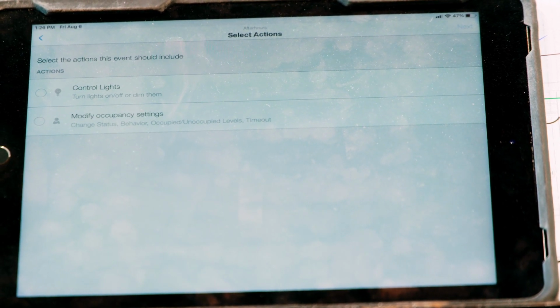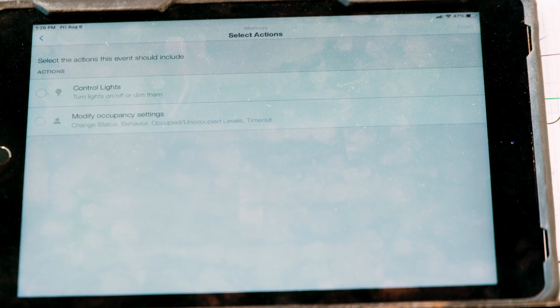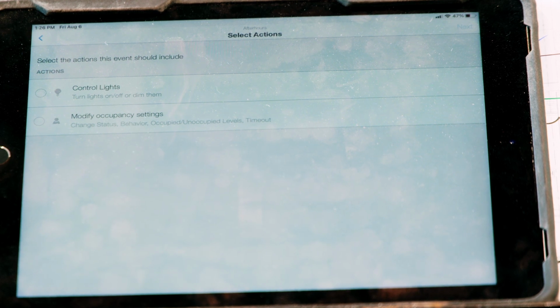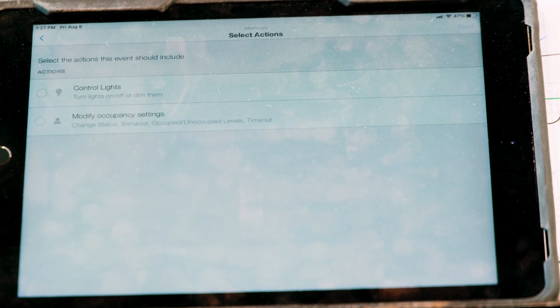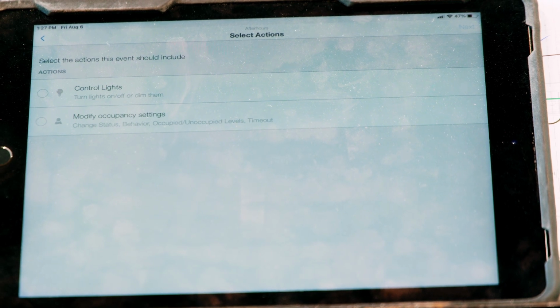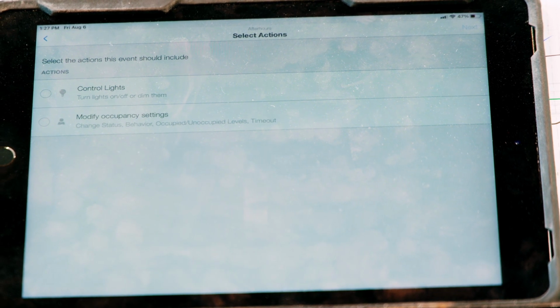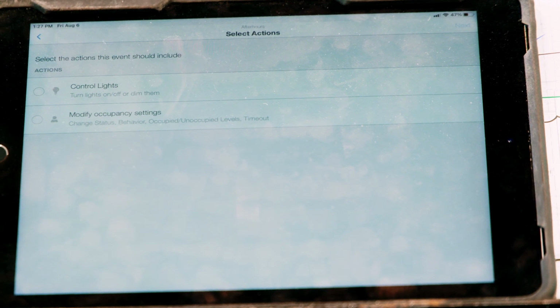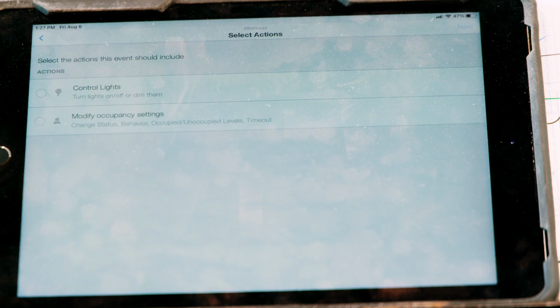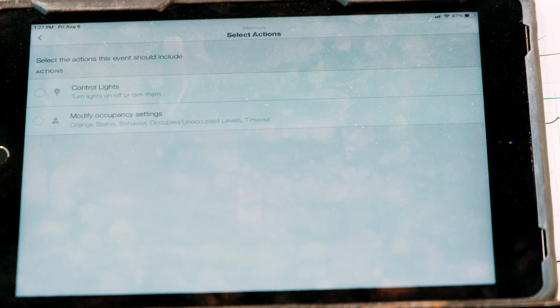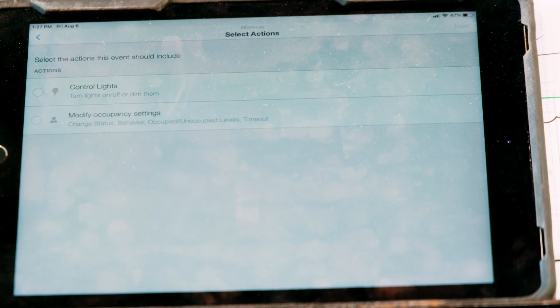If they hit the Pico when they leave, but if somebody comes in and hits the Pico, does that put everything back to normal operating? The Pico has no influence on the occupancy sensor, so the occupancy sensor stays in the state it's at. Let's say the occupancy sensor was triggered to occupied 13 minutes ago and the lights are dark when someone walks in. The occupancy sensor will pick up that person and reset its timer, so the 15 minutes starts back over. Then you can go to the Pico to turn the lights on. In bathrooms it would be good to set it to 5 minutes to shorten the time down a little bit.